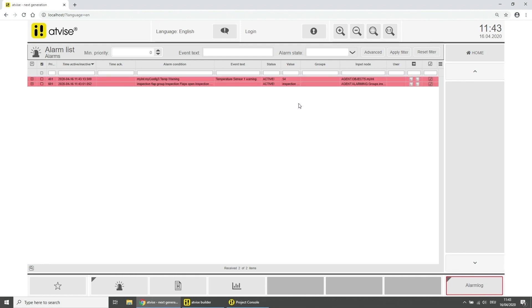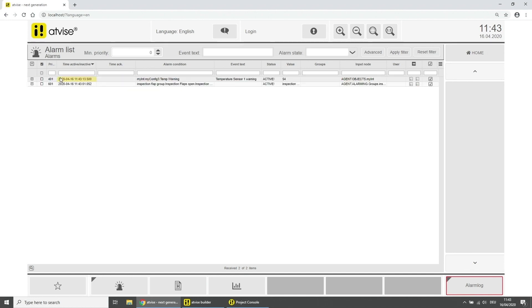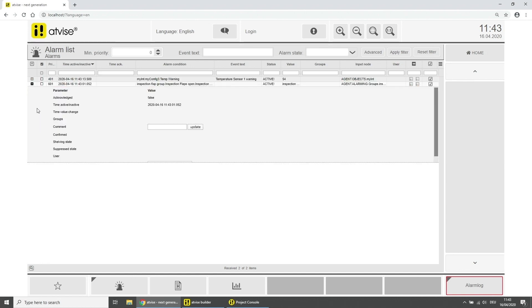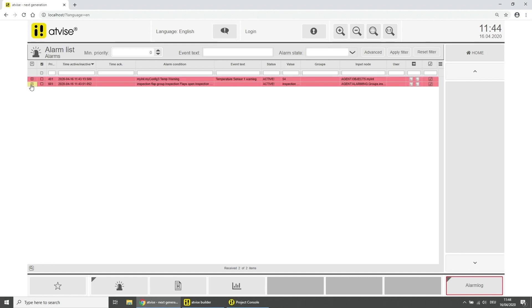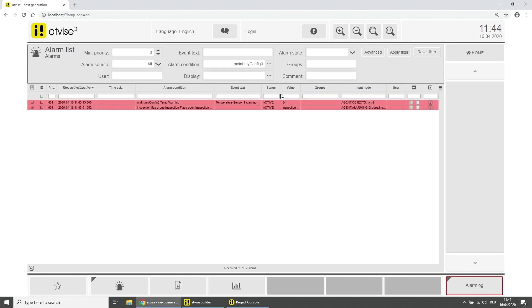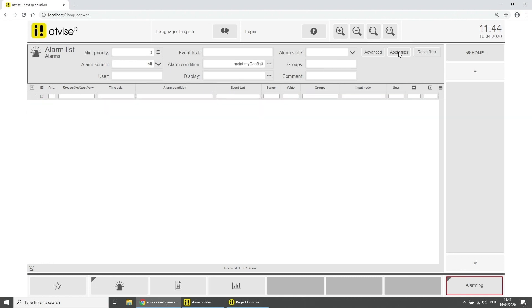In the new column you can see the source node of the alarm. By clicking on the column label you can sort the entries. Click on the error symbol on the left side of the alarm to get a detailed view of the alarm. To show all possible filters click on Advanced. To apply a filter, set the target value, for example an alarm condition, and then click on Apply Filter. To reset all filters click on Reset Filter and then on Apply Filter.